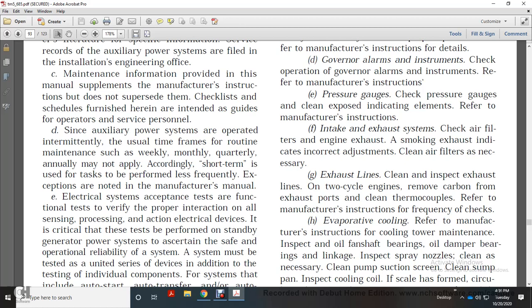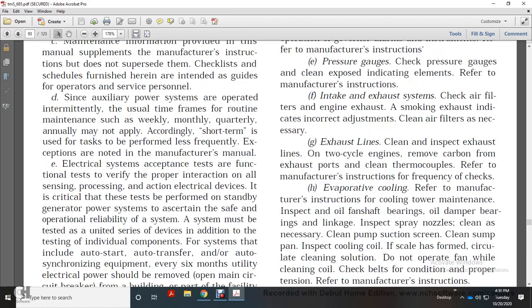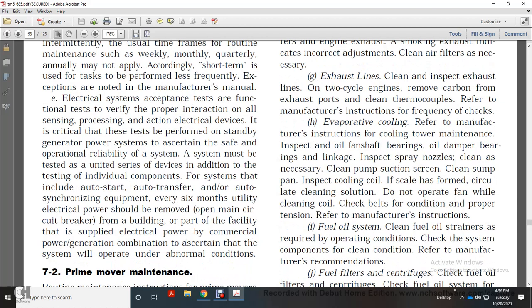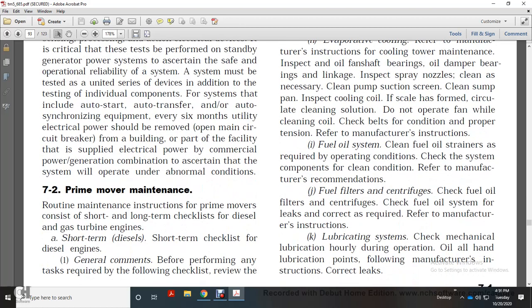Exhaust lines: clean and inspect the exhaust lines. 2-cycle engines: remove carbon from the exhaust ports. Clean the thermocouple, referring to manufacturer instruction. Frequency checks. Evaporative cooling, refer to manufacturer's instructions. Cooling tower maintenance: inspect the fan shaft bearing oil and damper bearing linkage, inspect spray nozzles and clean as necessary, clean the pump suction screen, and inspect the cooling coil, cleaning with circulating cleaning solution and not operating the fan while cleaning the coil. Check belts for condition and proper tension, referring to manufacturer's instruction.